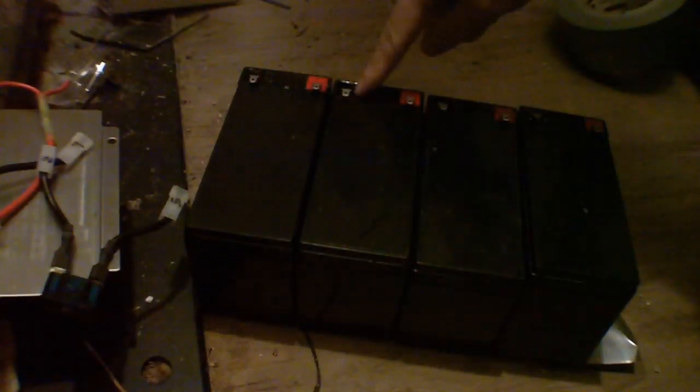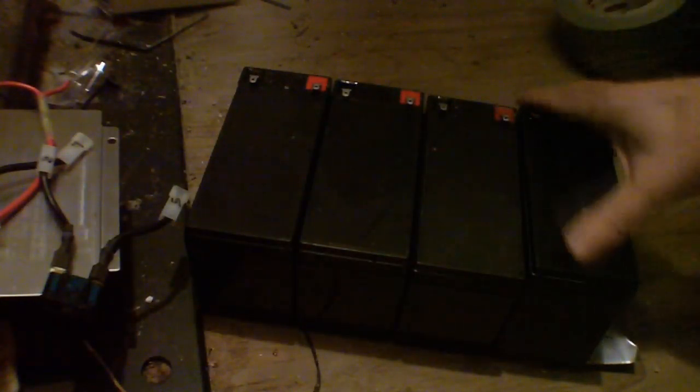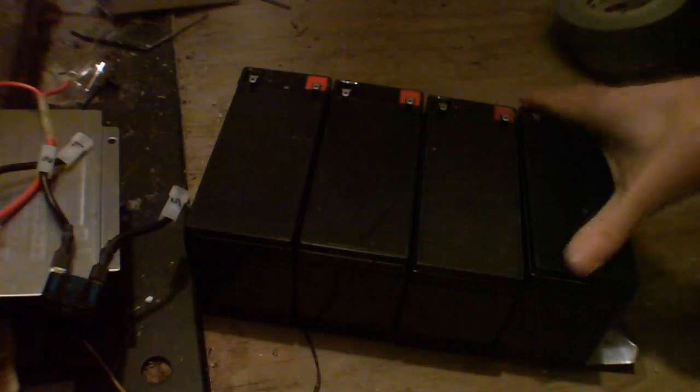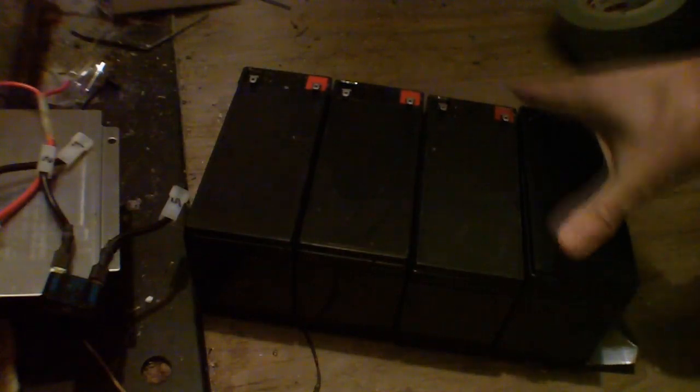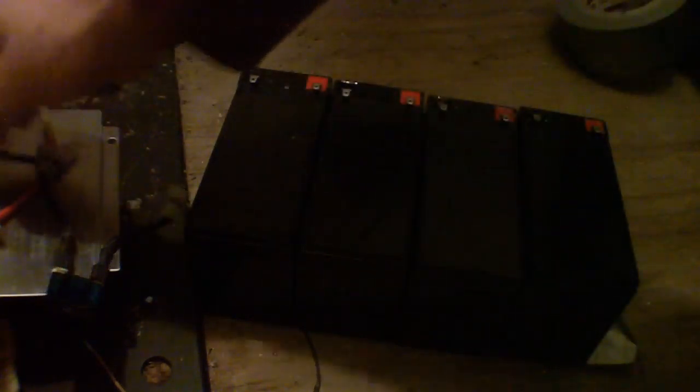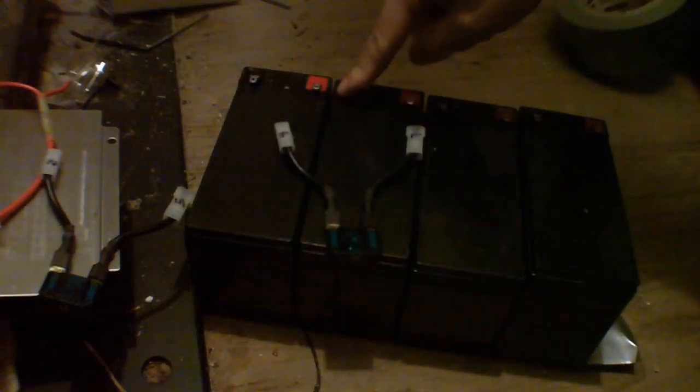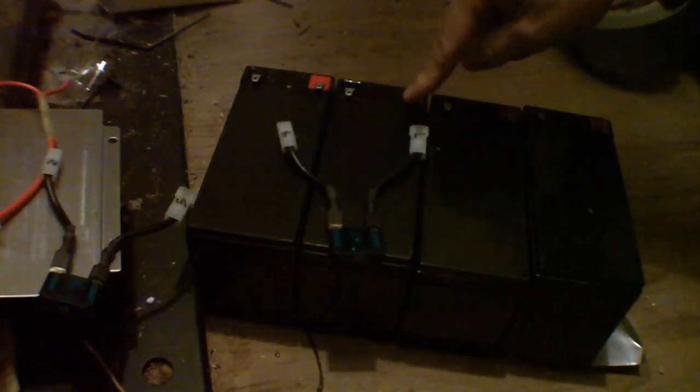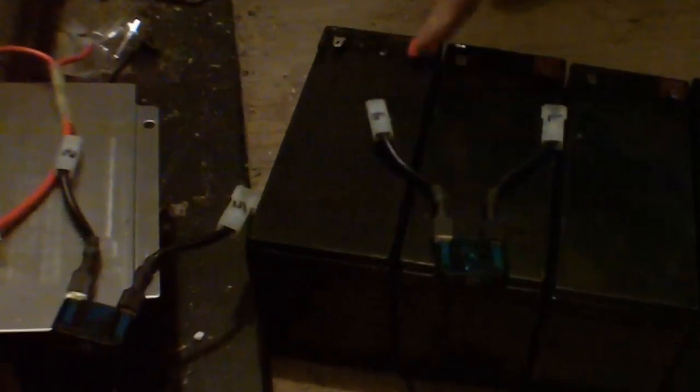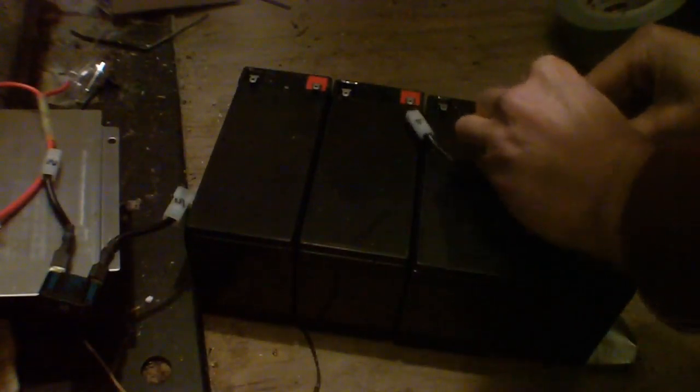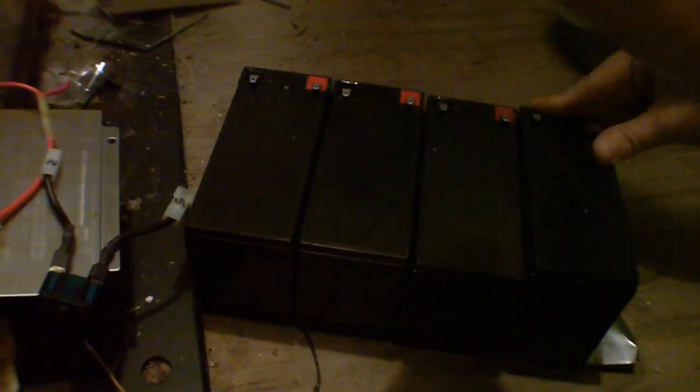Another note here: there are eight terminals, four negative and four positive, that have to be hooked up properly to the eight normally unlabeled wires that hook up the UPS. Well, before you remove the old batteries, be sure and use a permanent magic marker to label the terminals one through eight so you can match them back up and not blow up the unit or the batteries.